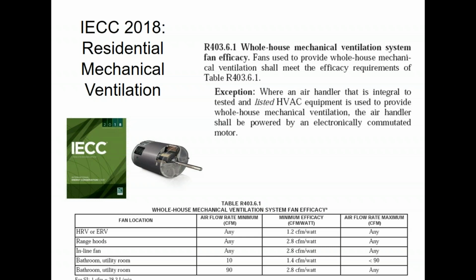If you do it that way, your air handler, i.e. your furnace, has to have an ECM motor. This was something we had to point out and force people to do with the Michigan and Illinois codes. It's not going to be a big deal for Indiana because, as you know, as of July 4th, I believe, last year, the manufacturers of furnaces now have to make all the furnaces with ECMs as the lowest entry point motor. So very shortly, you won't be able to find a PSC motor at your distributor anymore. So the problem just kind of goes away and takes care of itself.